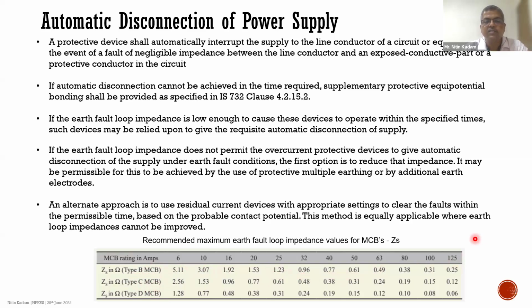Now, if the disconnection is not happening, then you can provide supplementary equipotential bonding. Further, if it is still not tripping, you can bring down the earth fault loop impedance values to substantially low values, so that the automatic disconnection of the protective devices happens. Further, if it still does not happen, then you can also use residual current devices. We will see on the subsequent slide how this can be implemented.